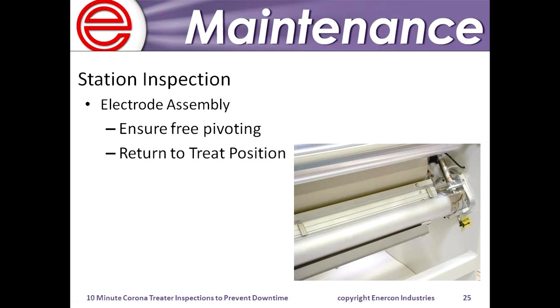Instead, you want to always make sure the electrode assembly is freely moving, that there's no mechanical restrictions once you go back into production. So always make sure that it's in the treat position, but more importantly, make sure that electrode assembly is moving freely. If there is a mechanical restriction, then you might need to drill down and see why, whether it's something locking it in place, or maybe the exhaust tube bearings need to be replaced, or something along those lines.